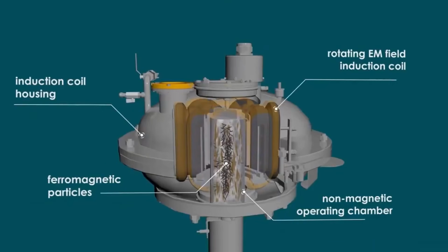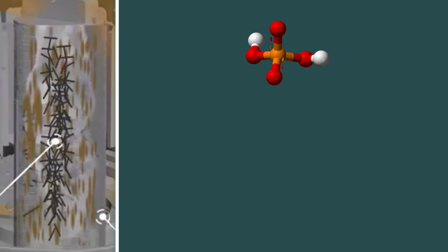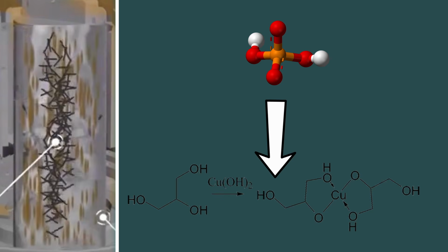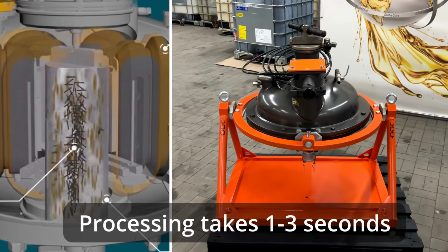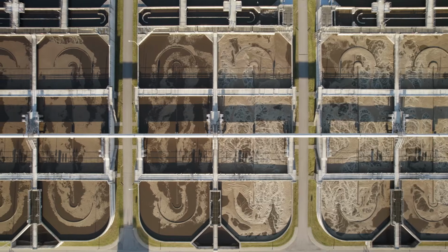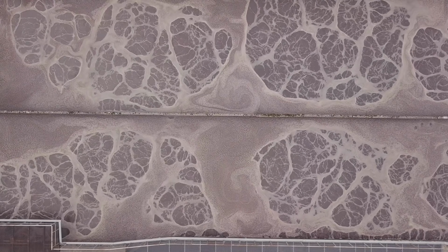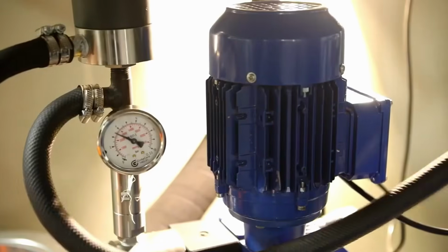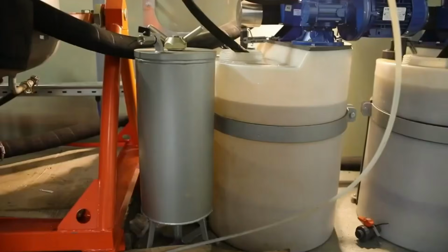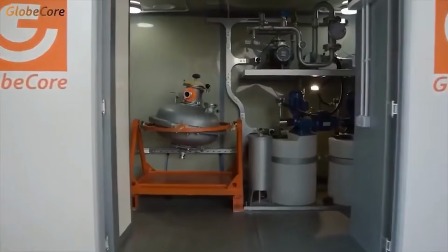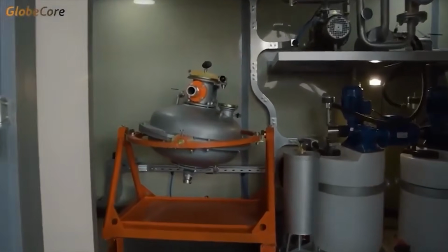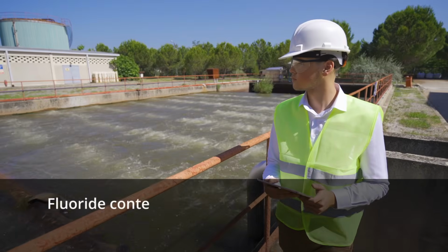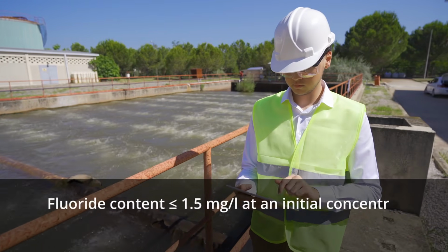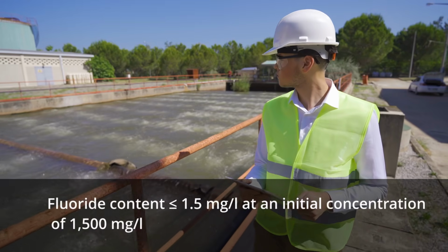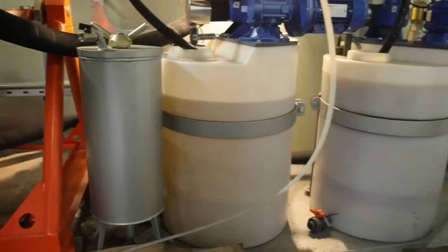While in operation, the vortex layer machine ensures rapid mixing and dispersion, as well as electromagnetic processing, which facilitates the defluorination and conversion of phosphates into water-insoluble compounds. The treatment takes 1 to 3 seconds, after which the wastewater is transferred to a clarification tank. The consumption of wastewater and lime milk is monitored by flow meters, and the pH level of wastewater, by pH meters. Owing to this treatment flowchart, the machine reduces the fluorine content of treated wastewater up to 1.5 mg per liter, with an initial value of up to 1,500 mg per liter, which indicates a high treatment efficiency.